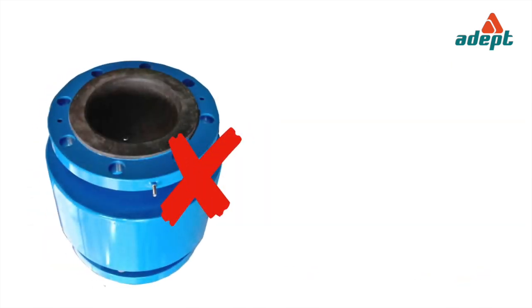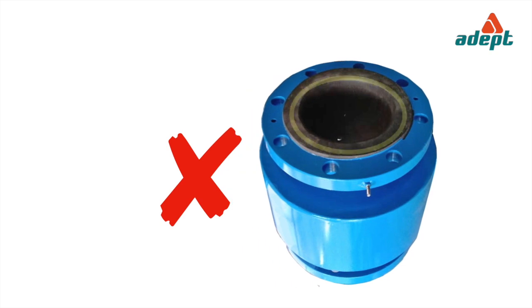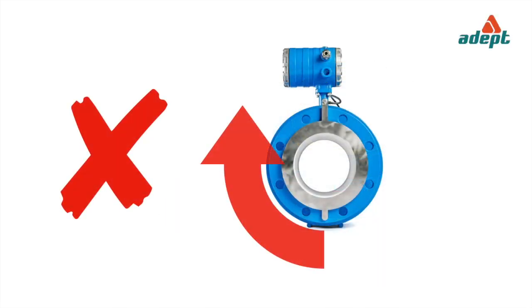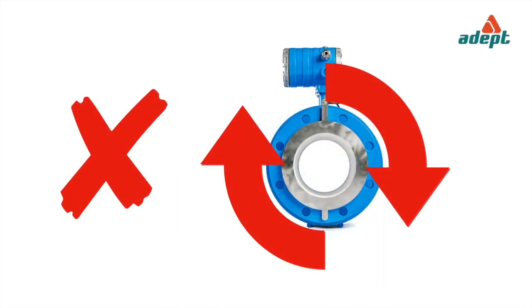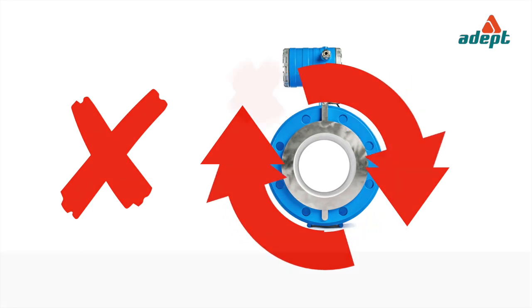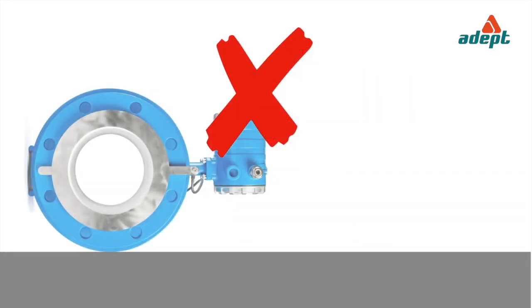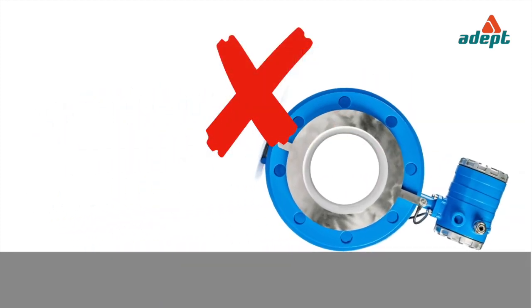Do not drag the flow tube with its lining facing the ground. This will damage the lining. Do not roll the flow tube over its flanges. This will damage the flanges and also the transmitter or the junction box.